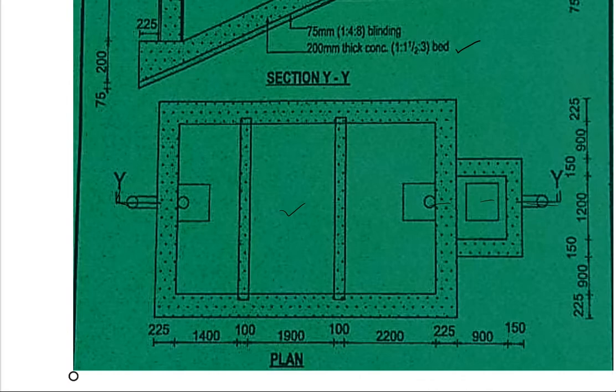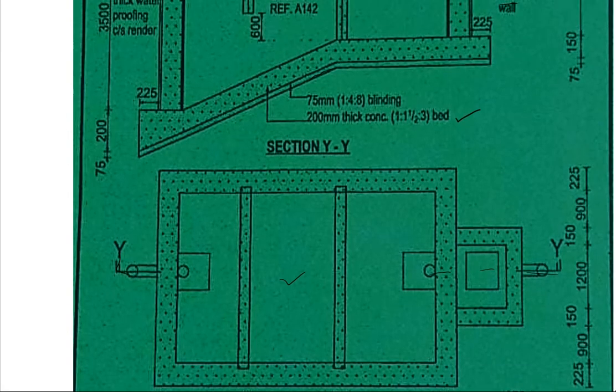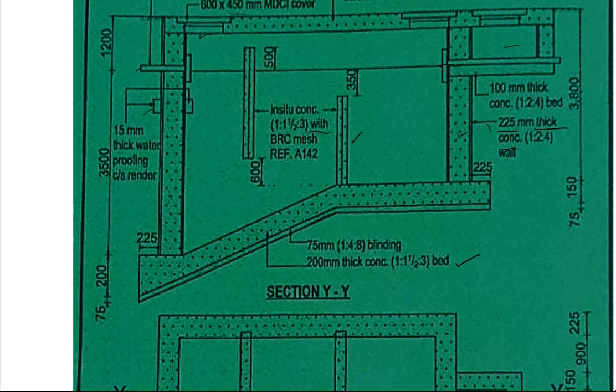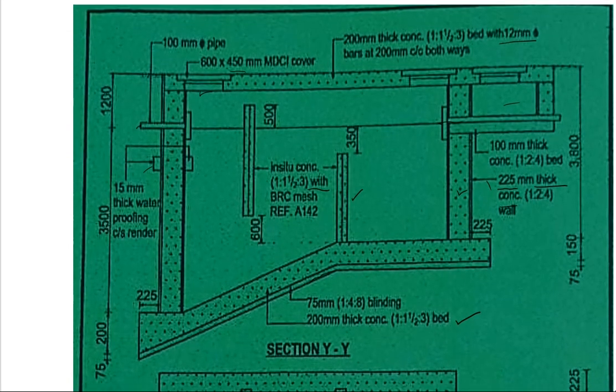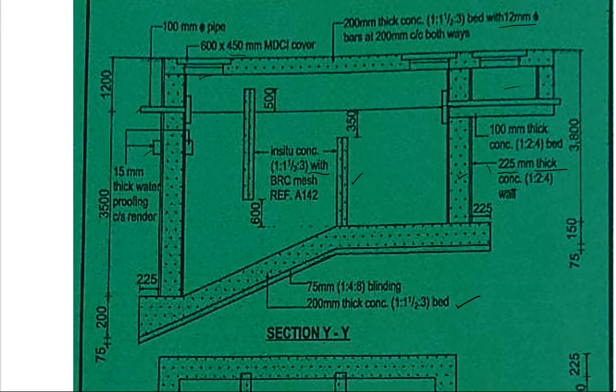We've been given Section YY so that we can get the fine details of the septic tank. Starting from the bottom: down here we have 75 millimeters blinding, and then after that we have concrete which is 200 millimeters thick, mix 1:1.5:3.